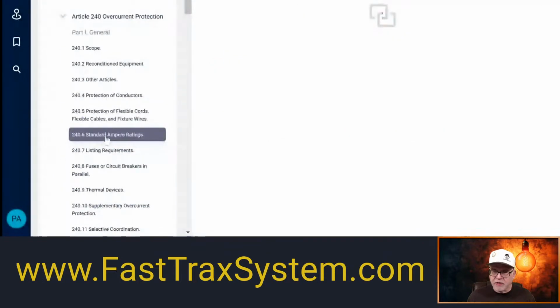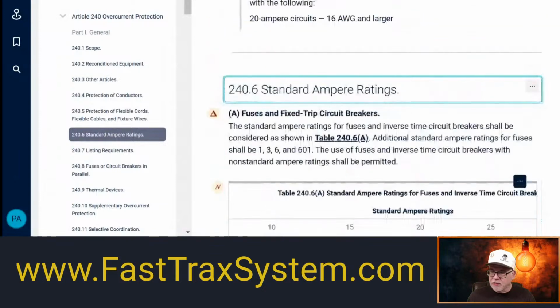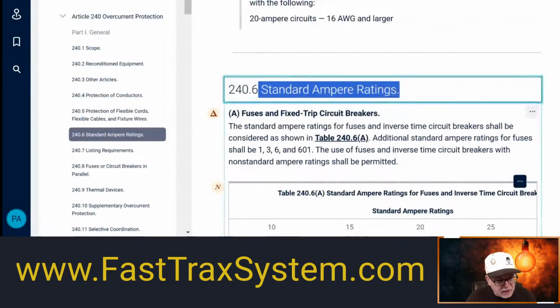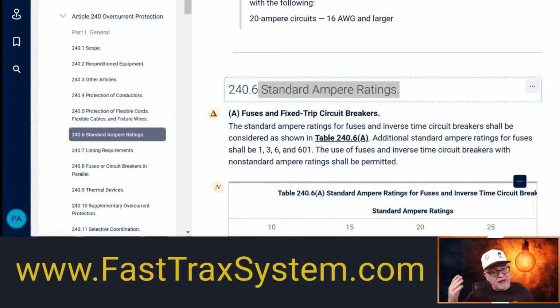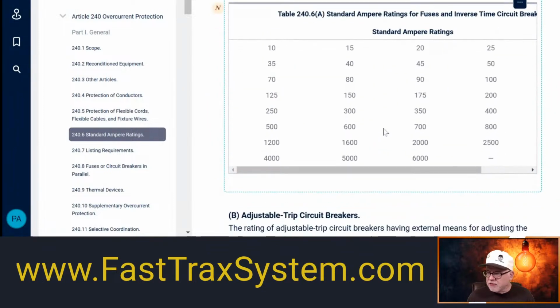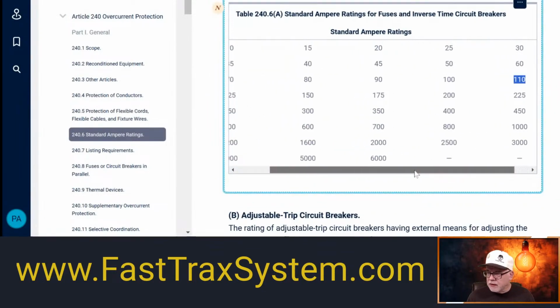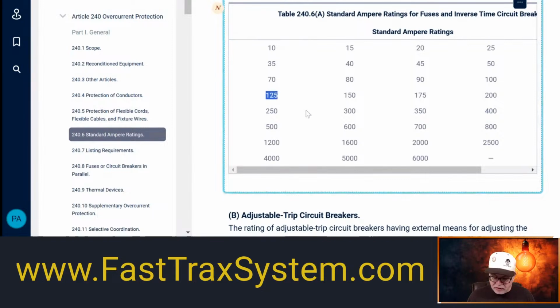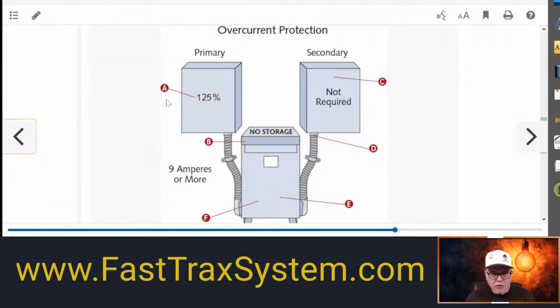This is a standard rating, okay? These are standard sizes. Can you find overcurrent devices in non-standard sizes? Absolutely, you can. They are available out there, right? But this is what the rule said, next standard size. So if I go down here to the list and I see I got a 100, okay, then it goes to 125. So I don't have any 112. So can I use a 125 amp overcurrent device, whether it's a fuse or circuit breaker? Absolutely I can. So we're going to have 125 amp primary protection. So let's take you back to here. So this primary protection is going to be 125 amps, okay?